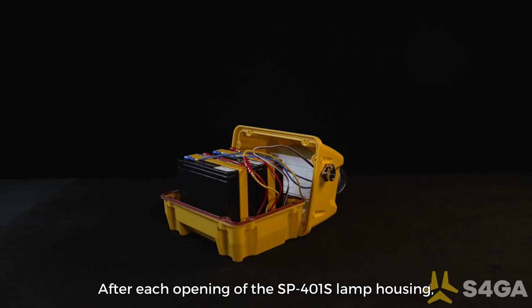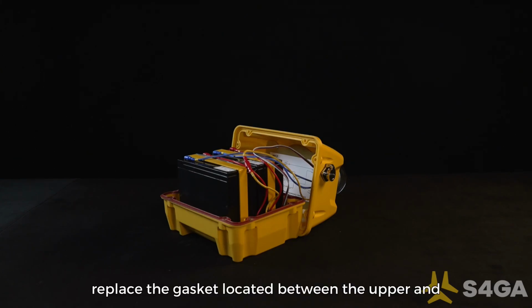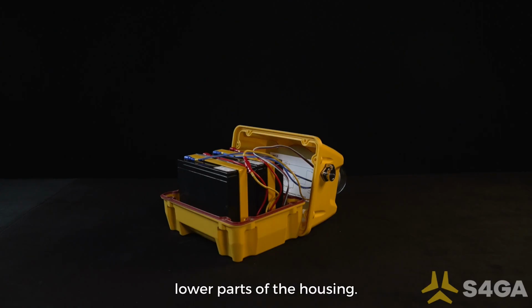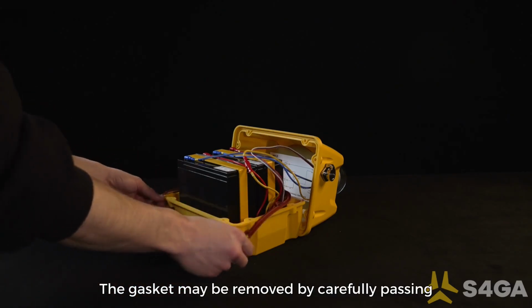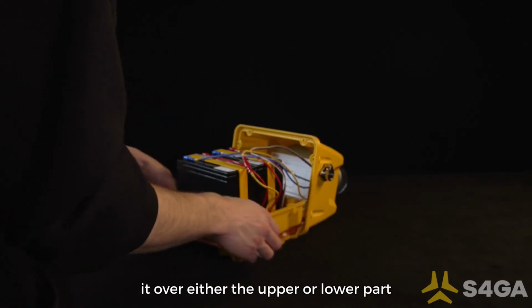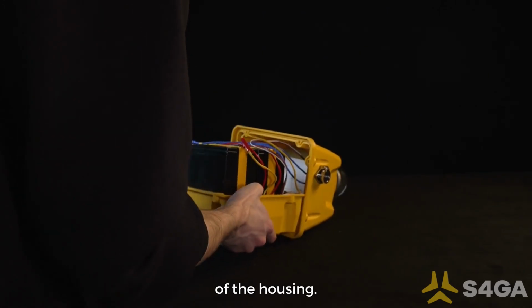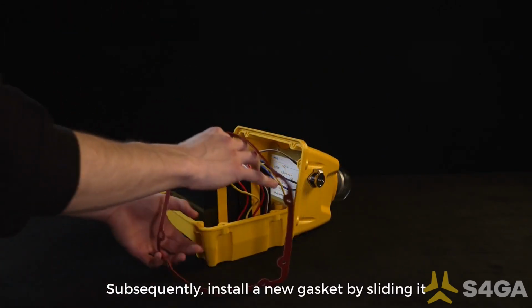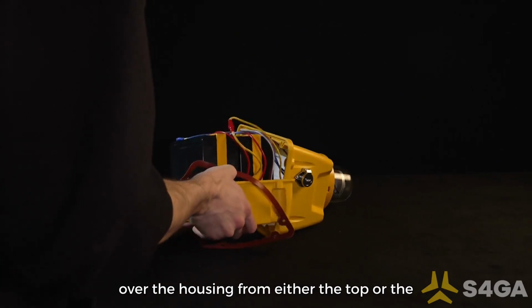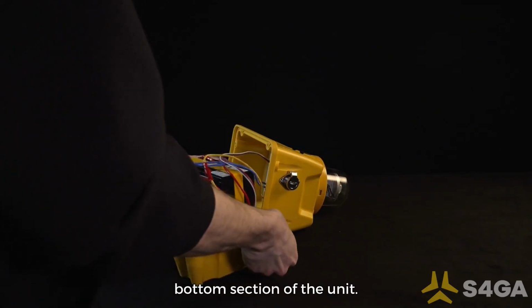After each opening of the SP-401S lamp housing, replace the gasket located between the upper and lower parts of the housing. The gasket may be removed by carefully passing it over either the upper or lower part of the housing. Subsequently, install a new gasket by sliding it over the housing from either the top or the bottom section of the unit.